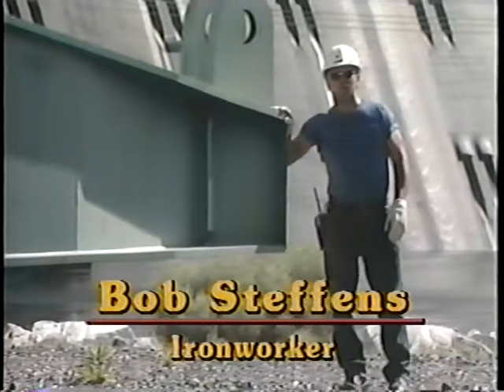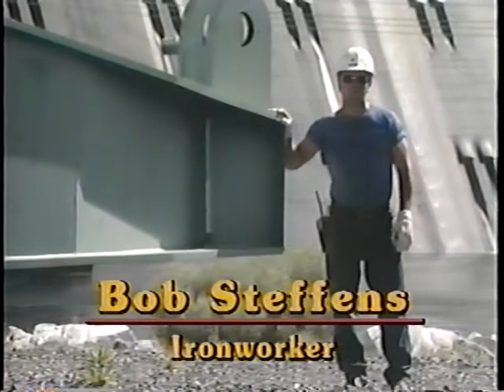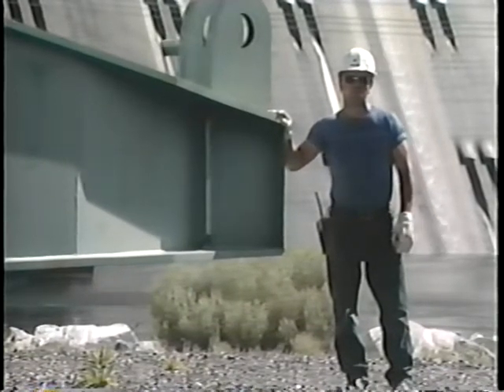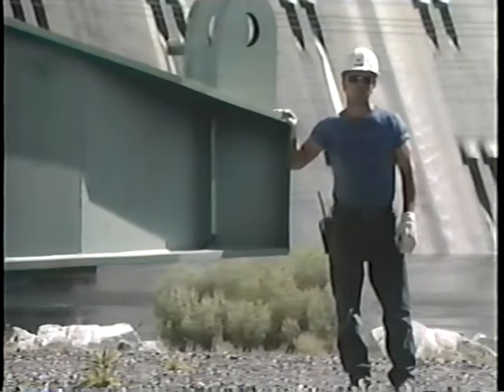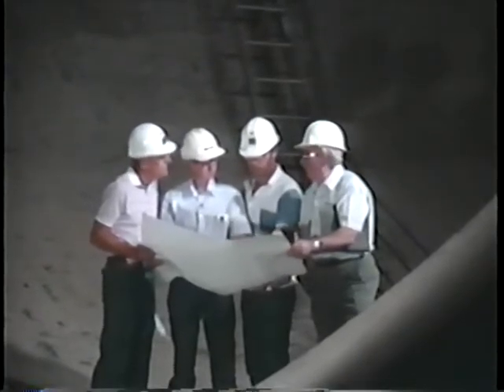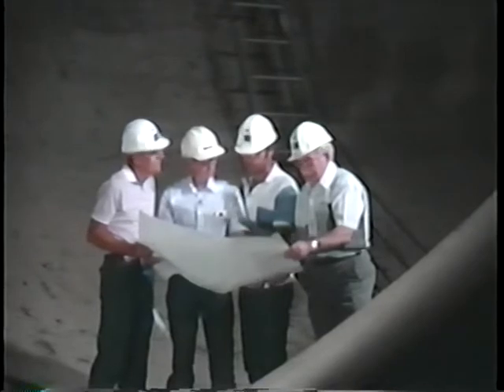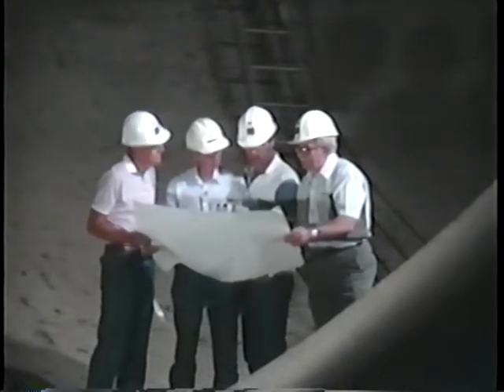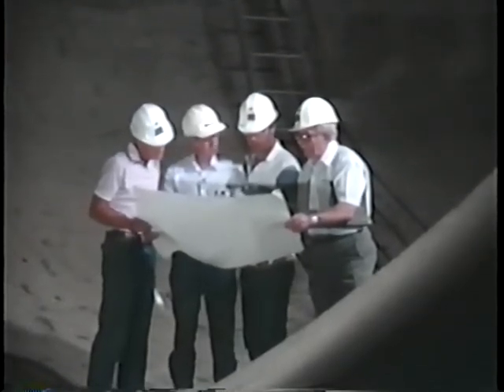What we do here at Grand Coulee Dam is very important to a lot of people in the west, even throughout the country. Whether it's performing general maintenance, repairing equipment, or replacing worn out parts, we always try to do the best possible job we can. We plan and schedule our work to keep outages to a minimum and to keep productivity high. If the machinists can complete the machining of the wicket gates by day 72, we can keep on schedule. We plan to work two shifts during this period and expect to finish the wicket gates about a week early. We'll need three days to get set up for machining the seal rings.